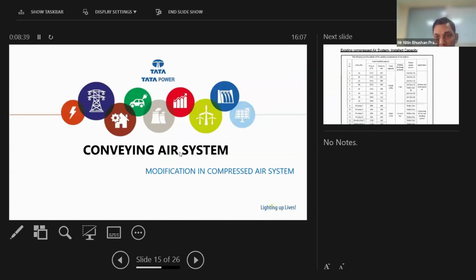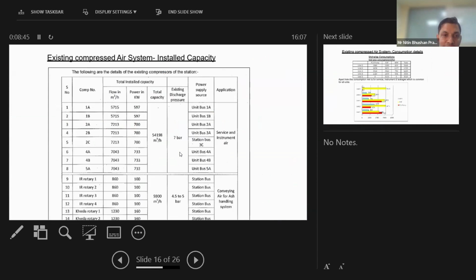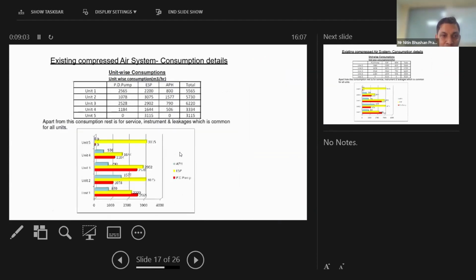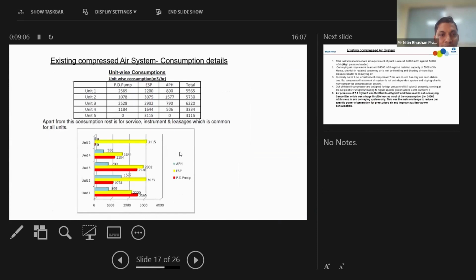This is one of the refurbishment plans that we had earlier. Basically, in JOJOBERA, we were having 8 compressors for instrument air and service air, and what we found in this is that all the compressors were made to run at around 7 bar pressure, and we had a kind of air audit in the plant itself.